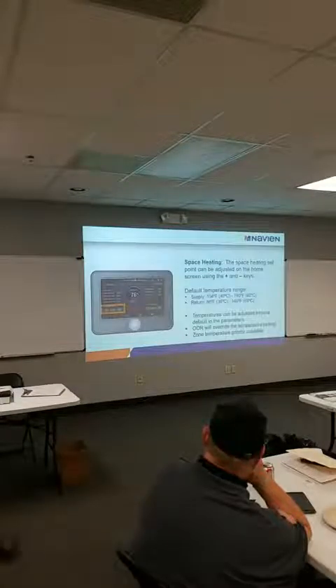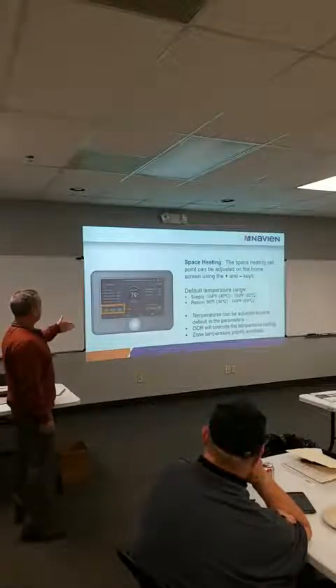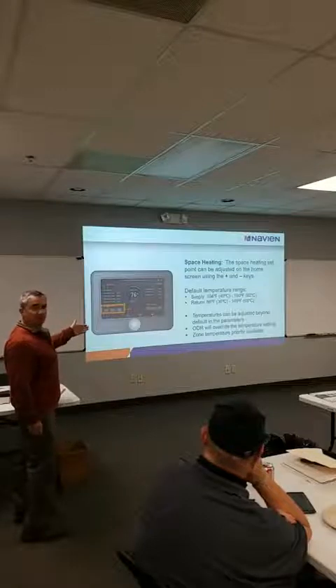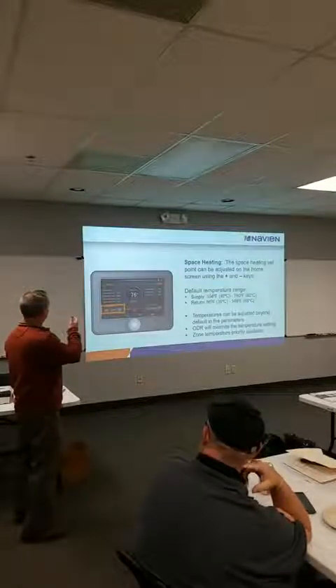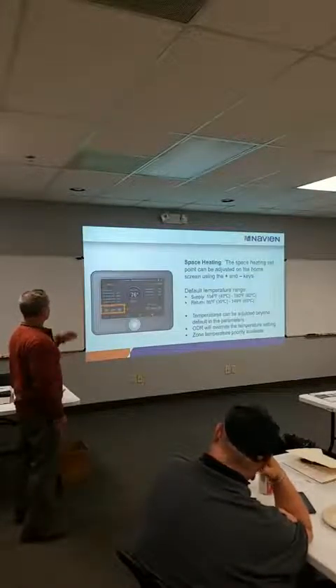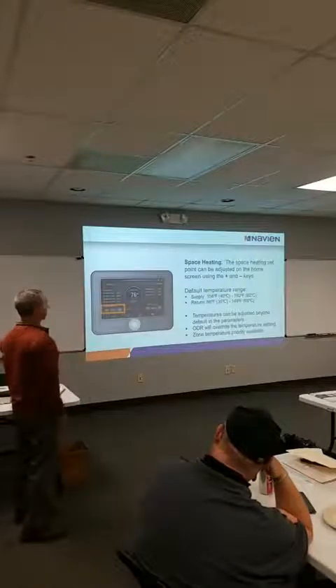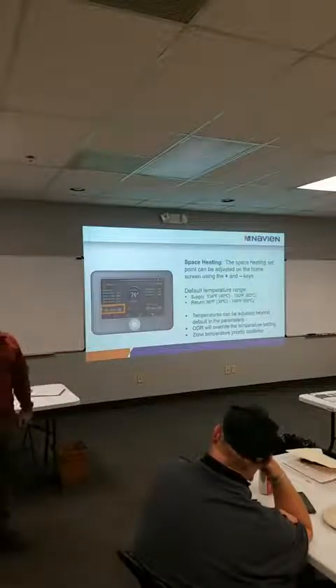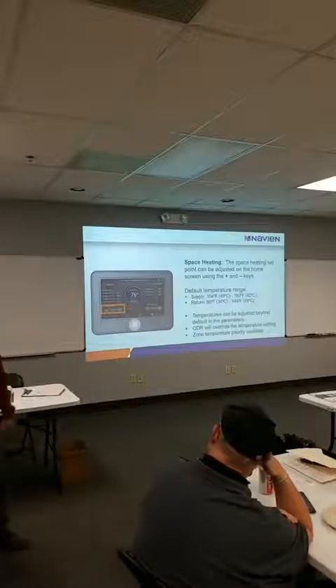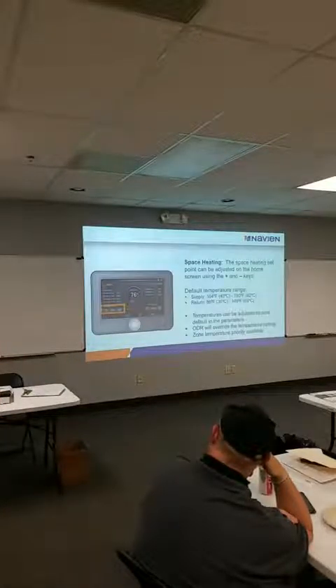So when you get into settings, this is your heating primary screen. It allows you to go in and change everything you could possibly want to change in there. It's going to show you how many pumps you got hooked up to the system. You can change how those pumps fire, supply temperature. You can change the percentage that this, all of our boiler equipment fires at.